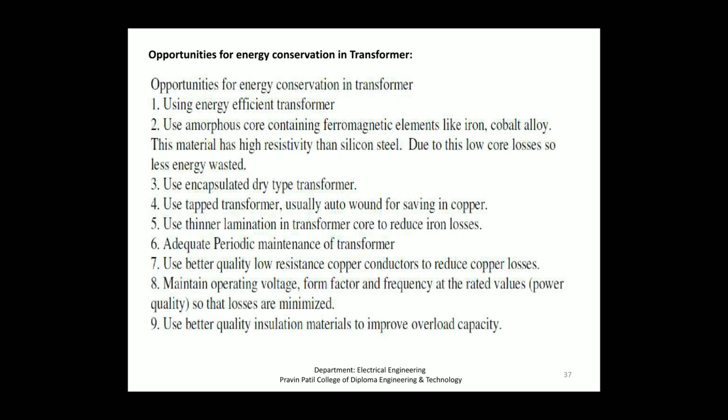Use thinner lamination in the transformer core to reduce iron losses. Adequate periodic maintenance of the transformer. Use better quality low resistance copper conductors to reduce copper losses. Maintain operating voltage, form factor, and frequency at the rated values so that losses are minimized. Use better quality insulation materials to improve overload capacity. These are the opportunities, or the importance, of energy conservation in transformers.